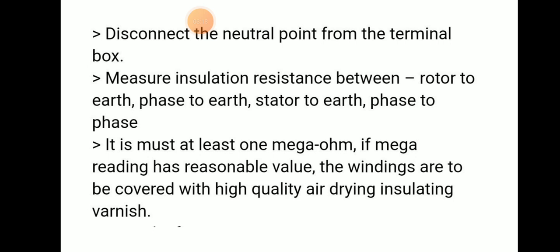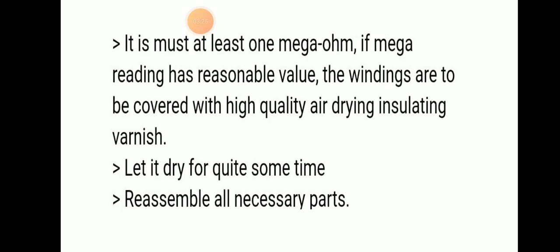If the Megger reading has a reasonable value, then the windings are to be covered with high quality air drying insulating varnish. If it is up to the level, then no problem. If not, high quality air drying insulating varnish has to be applied. Then let it dry for some period of time. Then we can reassemble all the parts after that.